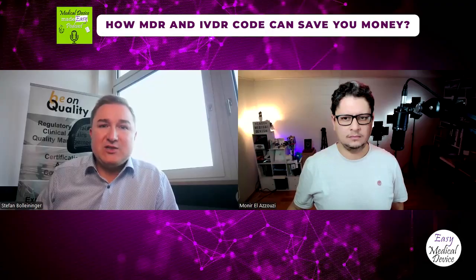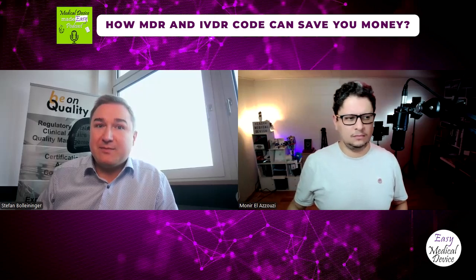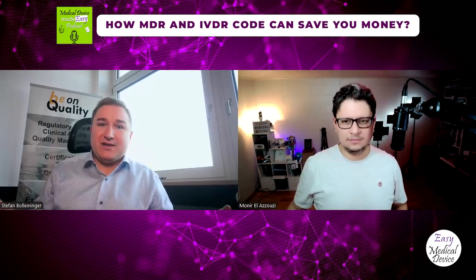These have specific ideas behind them, what your product's process is, like what you need to do during the certification procedure. If you don't find one of the MDT codes, which is quite often the case for most devices, just use MDT 2011 because that's labeling and packaging, and hey, all products have a label somehow.